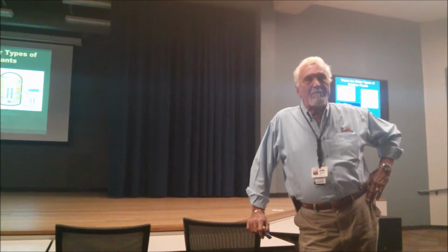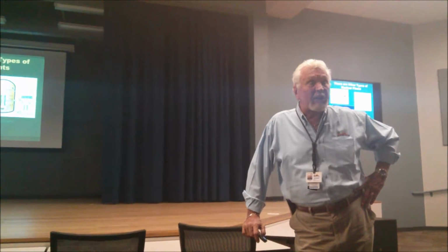Final question. Yeah. With respect to that, you may be biased in the answer to this, but with respect to the CANDU versus Palo Verde, which is the more efficient in terms of cost of kilowatt produced or megawatt? Palo Verde. Is it? The reason for that is because of economy of scale. CANDU, by its very principle and by the mechanics associated with it, not the physics of it, you're pretty well limited to about 700 to 900 megawatts capacity, whereas Palo Verde is 1,400 megawatts. So we've got an economy of scale in that.